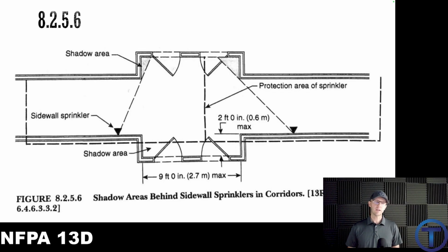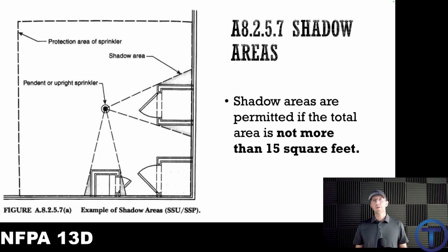We don't need to do anything extra as long as that recessed portion of the wall is 2 feet at the most. So if the wall protrudes in a little bit, we could still get the fire out in this sort of a corridor situation with doors. You can imagine this like apartments or something, you know, and the fire sprinklers will be able to put out that hallway.